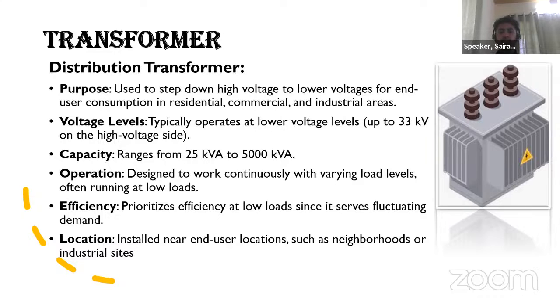The voltage levels are typically up to 33 kV, and capacities range from 25 kVA to 5000 kVA. These are designed to work under varying load conditions, because in the industries the loads won't be similar at all points of time. The fluctuating loads will be there. Even for fluctuating or lower loads, these transformers are designed to perform in a better way. From an efficiency point of view, at lower loads the efficiency of these distribution transformers will be higher. They are installed nearest to the end user location, so that there won't be any further transmission loss after conversion at the distribution transformer.